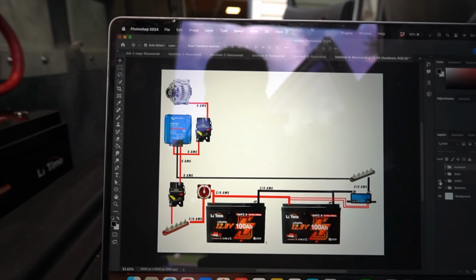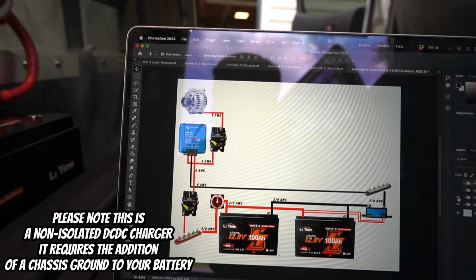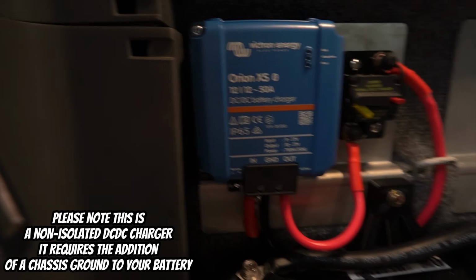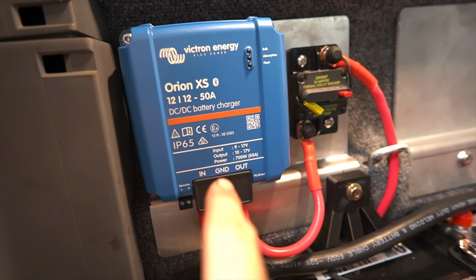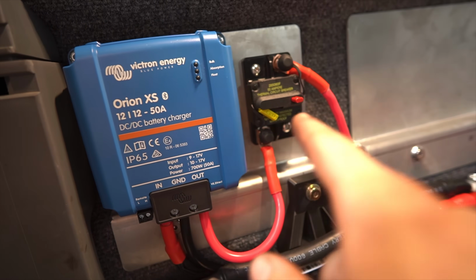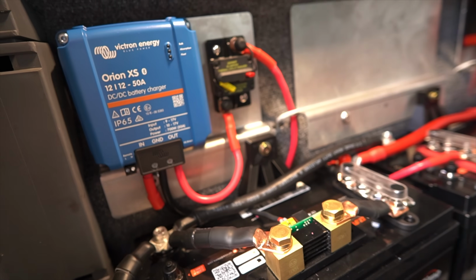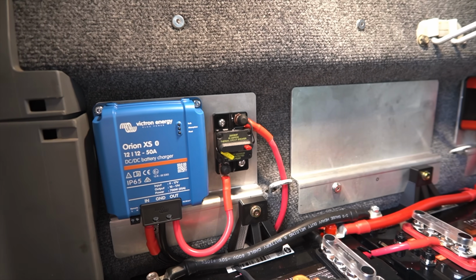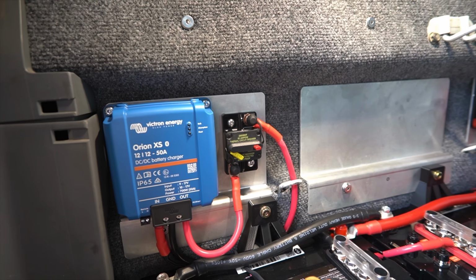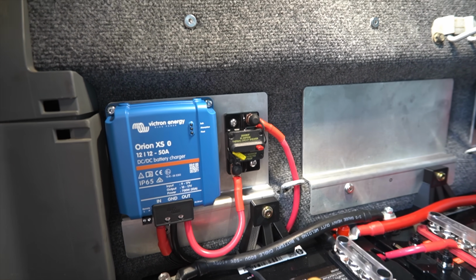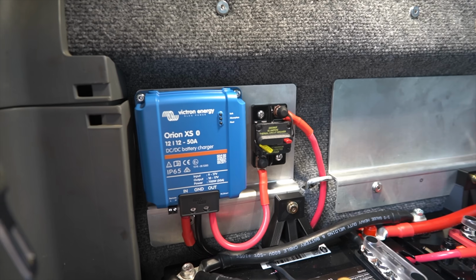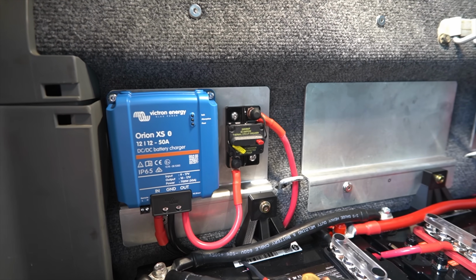So you can see from our bus bar, we have a circuit breaker, and that runs to the DC to DC charger, which is the out. So this is the power that's coming from the charger to a circuit breaker, and then to the battery itself. We have a circuit breaker on both sides just to keep everything nice and protected. The circuit breakers are 60 amps, so for a 50 amp charger, you just go 10 above for safety.